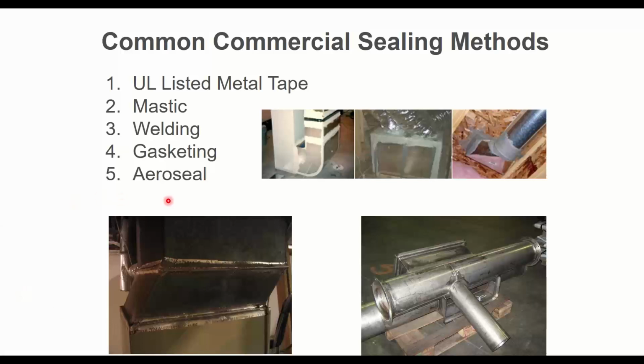And then you can aeroseal it. Obviously, the gasketing, you have to do as you're installing the ductwork. The welding, you pretty much have to do as you're installing the ductwork. Tape and mastic you can do after the ductwork is hung or existing. It's just hard to get back to that stuff. Aeroseal you will always do after the ductwork is installed. And it's the easiest one to do after installation, because you never have to get back to ductwork that's buried. If it's in a wall cavity and you can't get to it, you don't have to bust the wall open. That's totally fine.